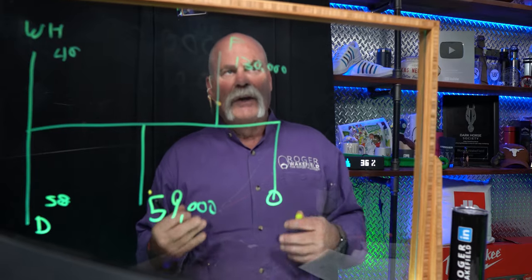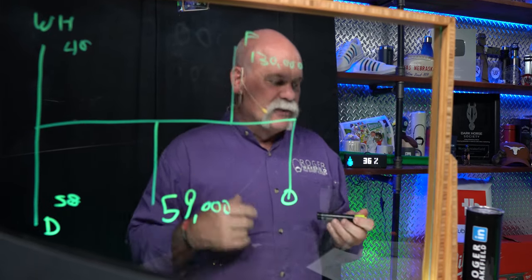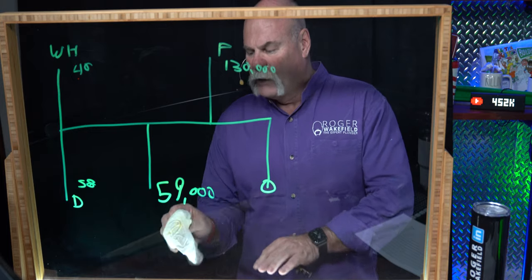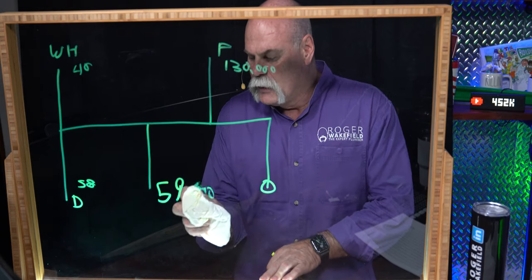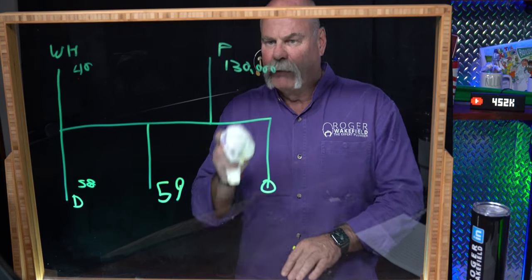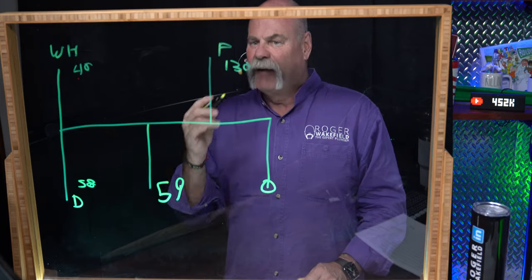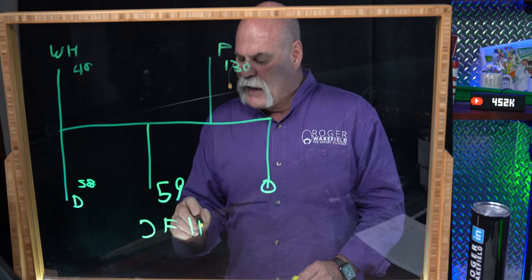To get cubic feet per hour, you divide each BTU value by 1,000. So we're looking at 40, 58, 59, and 130 cubic feet per hour. This is what I'm going to build my entire system on.